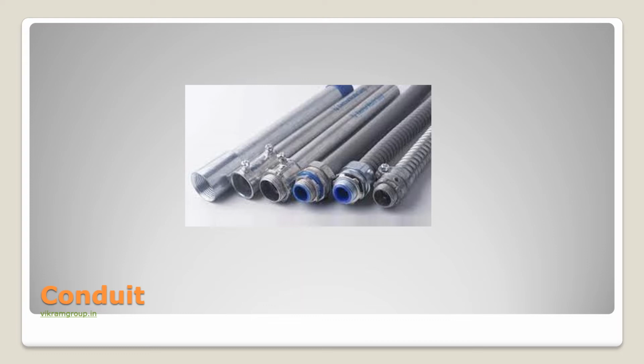In the next couple of examples there, going sort of to the middle of the photograph, you see some examples of electrical metallic tubing. Electromechanical tubing is much thinner, so it's easier to bend. It's also lighter. But because it is so thin, we can't thread it. So we use a mechanical fitting like the ones you see there that are attached with a screw. Essentially, you position it over it, you tighten the set screw, and it holds it together, and it provides a good mechanical connection, but it's not as robust as the threaded fitting you see on the far left.